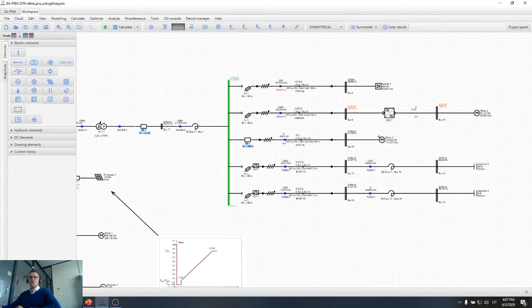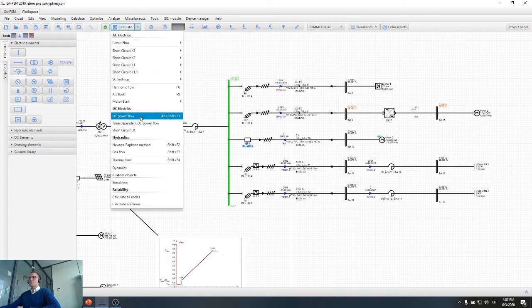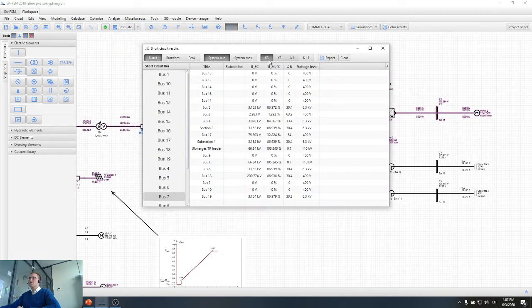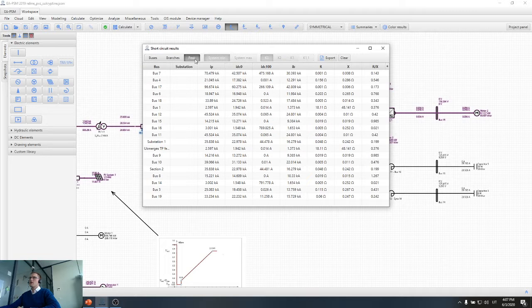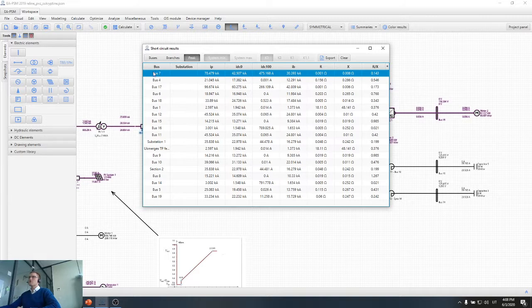There was one more question, how to calculate the DC component of a circuit breaker during asymmetrical short circuit. So the DC component is not calculated for the asymmetrical short circuit because the worst case scenario is during symmetrical three-phase short circuit calculation. When I calculate three-phase short circuit, I can go to peak values of the short circuit, and let's say we have a short circuit at bus 7, the software provides information about the DC short circuit current component at time 0. Basically it is equal to 42,000 amps. After 100 milliseconds it will be equal to 475.